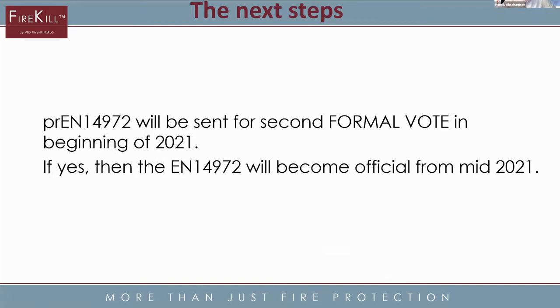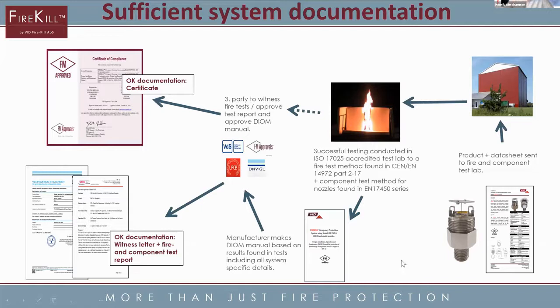The next step for EN 14972 will be that it goes out for a formal vote, probably at the beginning of 2021. If it ends up with a yes, then hopefully we will have an official European standard to go on with. How do you work with it? You start with a product, go to the ISO 17025 accredited test lab, choose a fire test method found in parts 2 to 17, do some component testing as well, and from these tests you make your DIOM. Everything you find in the fire testing and component testing will be reflected in the DIOM — the design, install, operation, and maintenance manual.